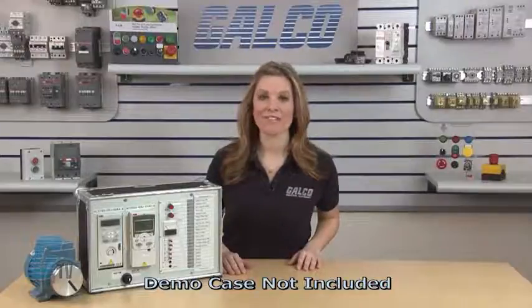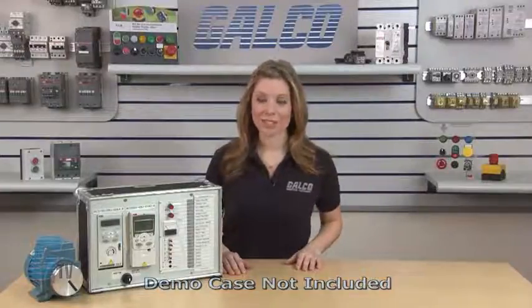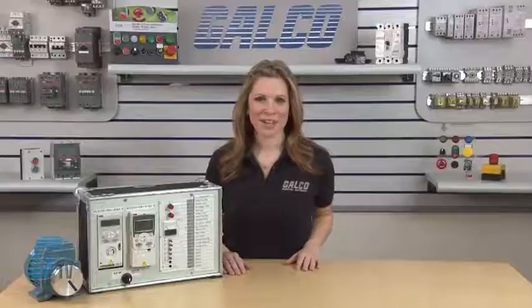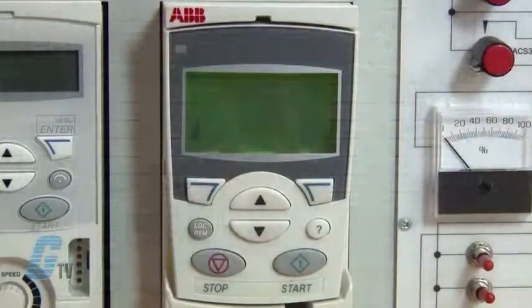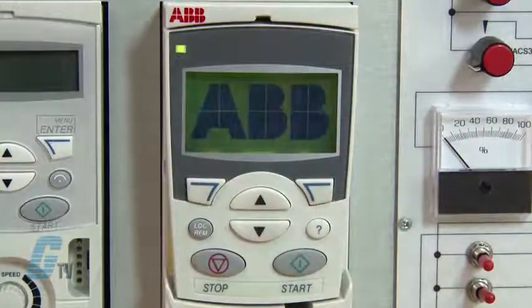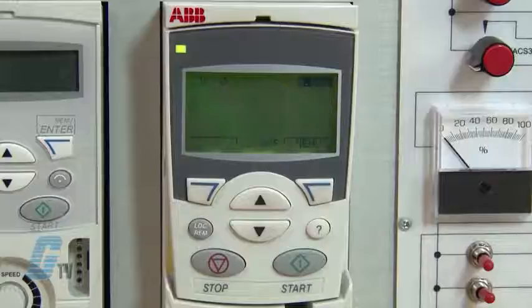Today I would like to demonstrate how to do a basic startup and operation of an ABB ACS 355 AC drive using the advanced control pad. After verifying that the wiring is correct, I can apply power to the drive to begin programming. This particular drive has an advanced control pad mounted to the front as opposed to the basic control pad.